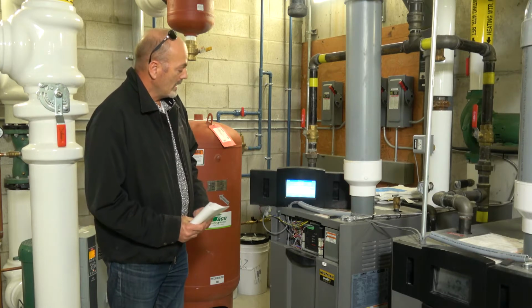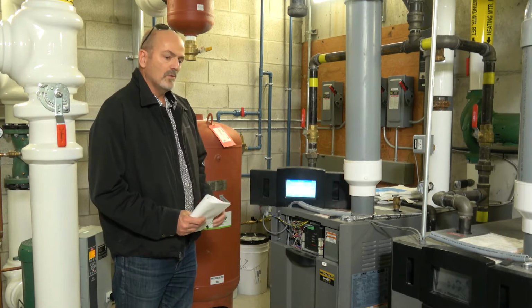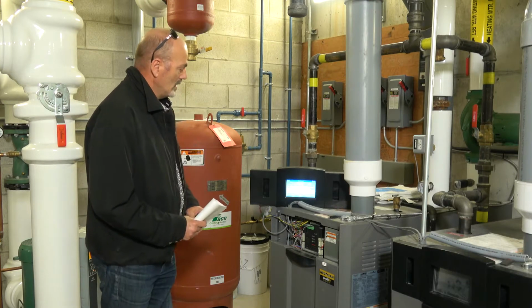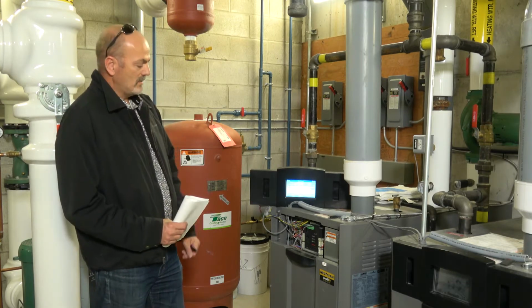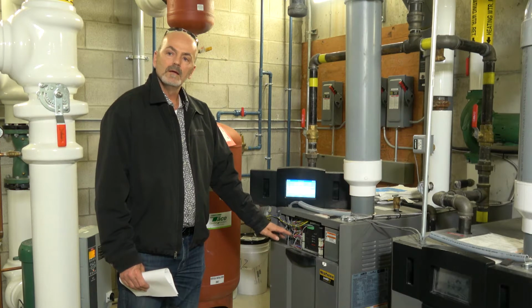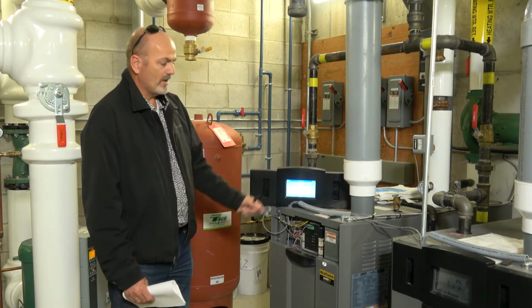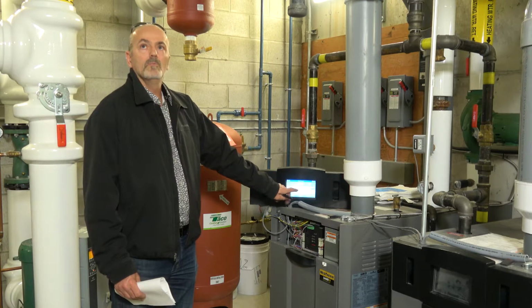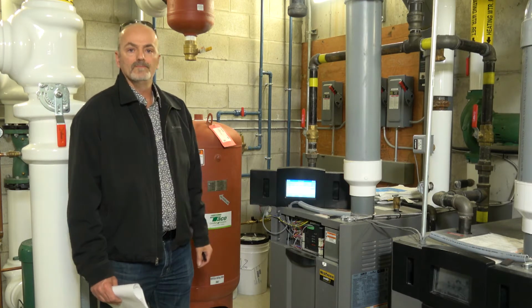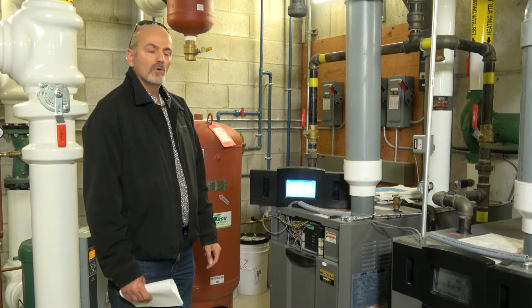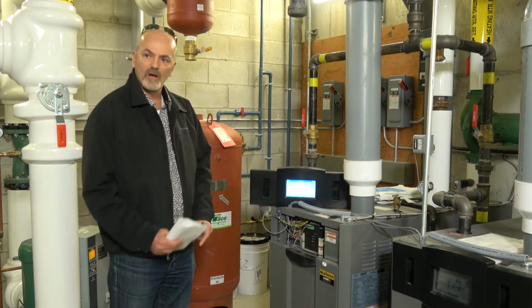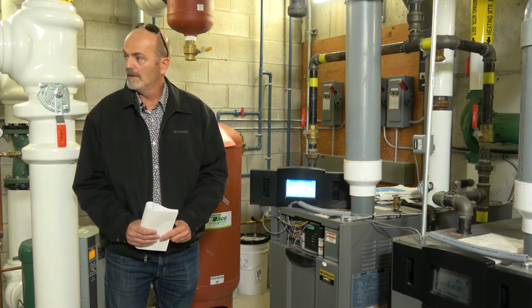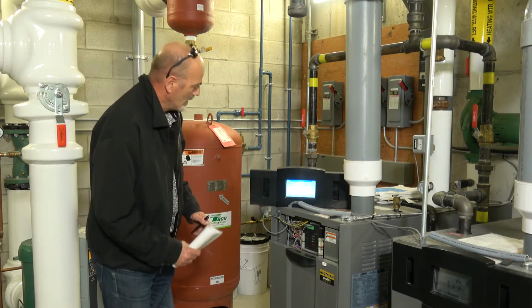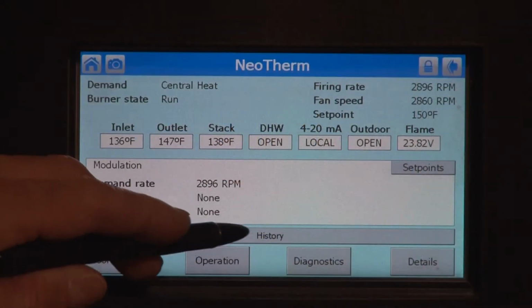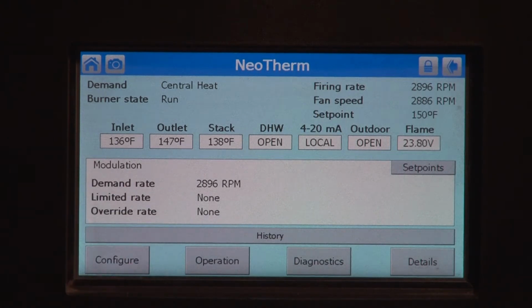When the boiler is running, the display will indicate that it's in a run mode. When you first show up to the display, it will be basically blank. You touch the display and it comes up, then you press the little blue control module in the middle, and your home screen comes up with all the necessary parameters. If there's a fault, it will show up where you currently see history in blue. That will change color and a fault will be registered.